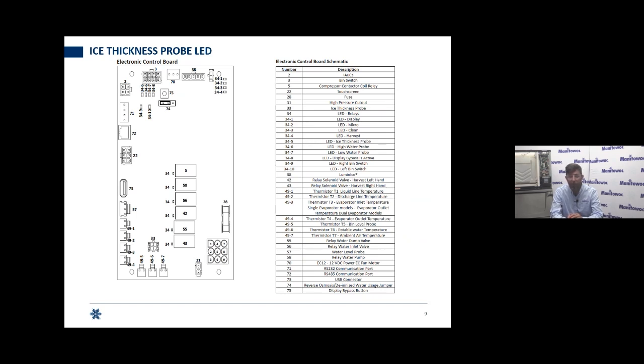The Indigo and the Indigo NXT use an acoustic probe, so it's listening to that ice. It can hear the sound the ice is making as it forms. So that light does not serve the same function on an Indigo or an Indigo NXT that it served on the S model and before. So do not use this light for troubleshooting. That light can be lit when this probe is calibrating, when it's sensing. I've seen it lit in harvest. We do not utilize this light to troubleshoot the same way that we did on the S model, Q model, J and B, and any other machine that used either a single wire or dual wire water sensing ice thickness control probe. So do not use this light for troubleshooting.